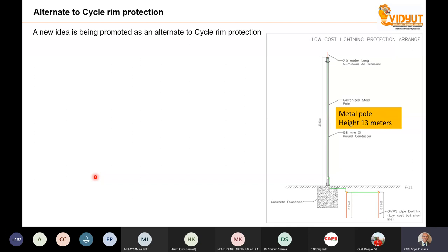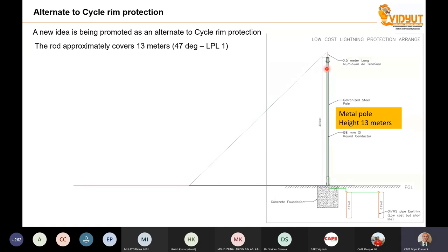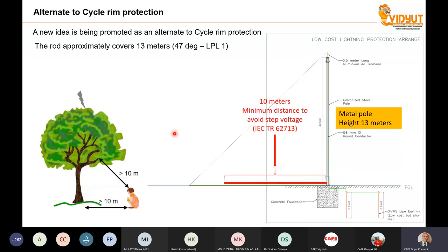In the new system, instead of a cycle rim, they have proposed a GI pipe, and then there is a 0.5 meter long aluminium air terminal, some down conductor, and some earthing system. Now you read at the earthing system, GI MS pipe earthing, low cost but short life. So that means after 2 years, the earthing is gone. Will it work? Let us analyze. This rod, as per the theory which is shown in the previous slide, if we take a level 1 protection, protects up to a 13 meter pole, 47 degrees. So what I am showing in this dotted line is approximately the area which is protected.